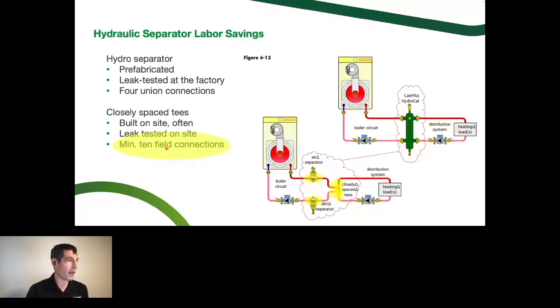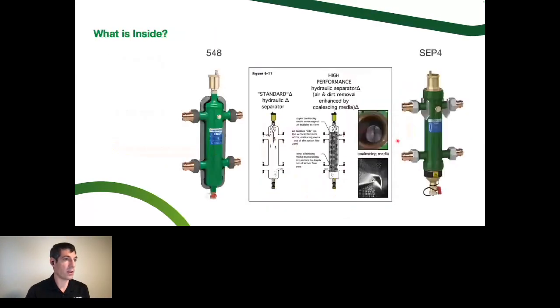I would say realistically, the labor to do 10 field connections with air, dirt, closely spaced tees, 10 minimum connections to get this together, and as we talked about with that proper spacing and things like that, may mean a more expensive total installed cost compared to a hydro separator where you've got 4 union connections that you can use press or sweat or NPT and kind of keep moving. All of this has been pressure tested and tested for functionality by whatever factory you buy the hydro separator from. So there's some peace of mind there that if something leaks, it's going to be a warranty item and not just installer error. If you have a leak with your closely spaced tees, you're not going to get any money back from a brass company. That's kind of on you if there's a leak in that system. So I would argue that factoring in the labor, the hydro separator may seem like an expensive purchase price at the wholesale house, but there's high potential that it would be less expensive to get it in and commissioned properly.